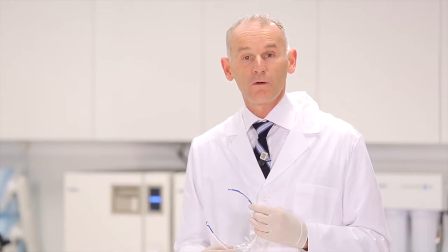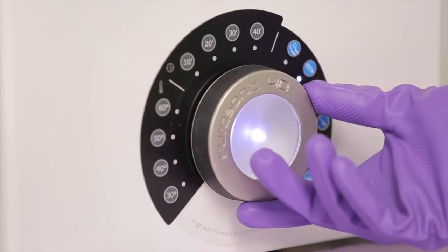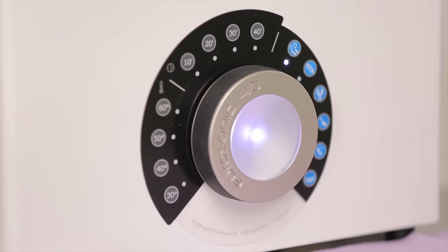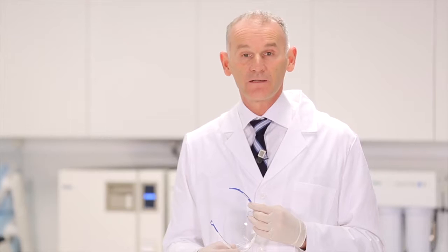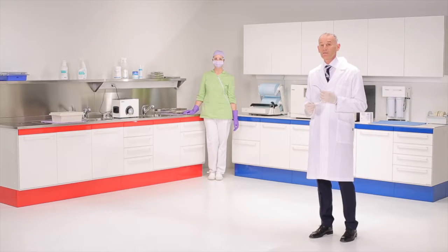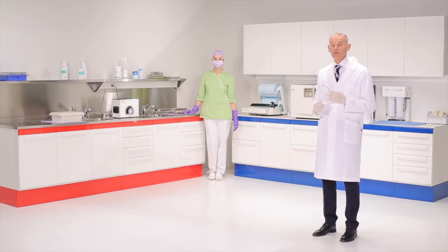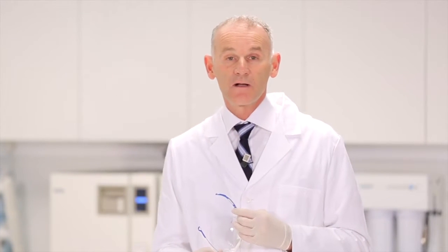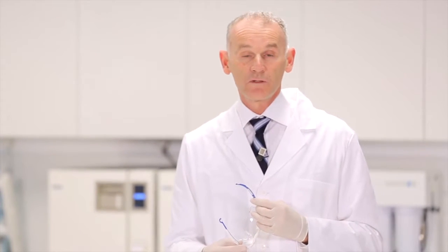The Euronda Eurosonic 4D ultrasonic tank enables the temperature, action times, and up to 6 cycle settings to be selected. When the action time of the ultrasonic has expired, the assistant will proceed to rinse the instruments and then dry them. Drying can be done manually with a microfiber towel and compressed air, or through the drying stage included in the thermo-disinfector cycle.